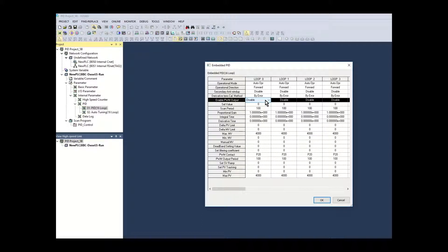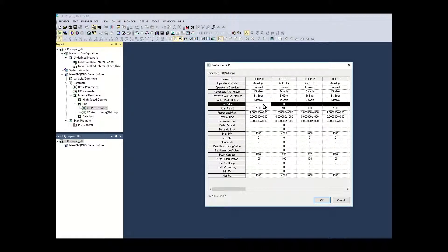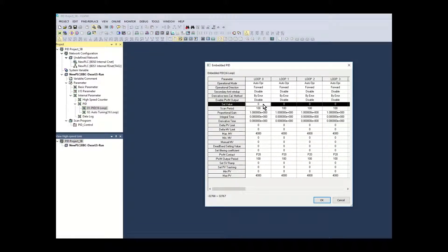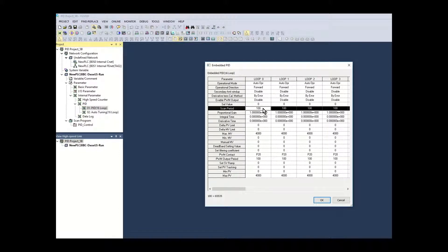Pulse width modulation is disabled as analog control will be used for the MV output. The initial set point value is left at zero. This value will be set during autotuning. The scan period is set to 100. This is a 10 millisecond calculation cycle.